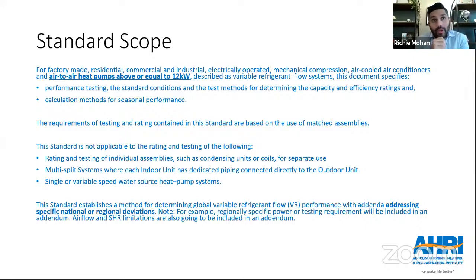...just measuring the cooling side of the overall system, where you go through the cooling conditions. There's a provision on the heat pump side, so you'll have to test in accordance with both cooling and heating conditions. And then for simultaneous cooling and heating conditions, there's consideration of adding another metric, the simultaneous cooling and heating efficiency, or SCHE in short, which looks at the performance of your heat recovery module.